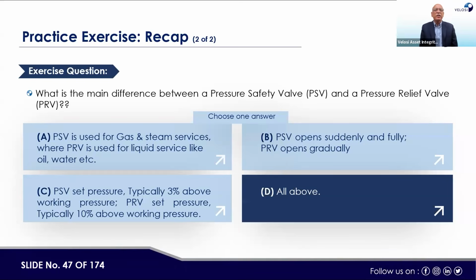Like PRVs and PSVs: PSVs are used for gas service. PRVs are used for liquid service. PSV opens suddenly, whereas PRV opens gradually. PSV set pressure generally 3% and above, could be 10% also. There is a discussion. And generally PRV is at 10% above working pressure.